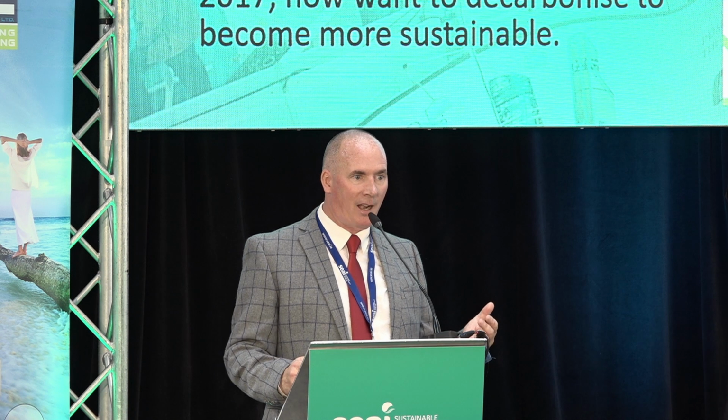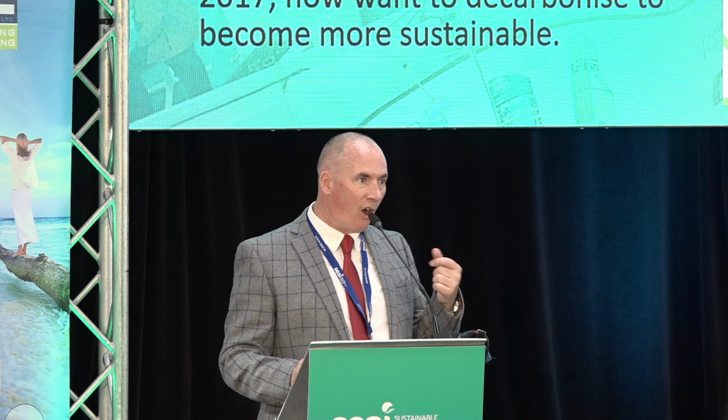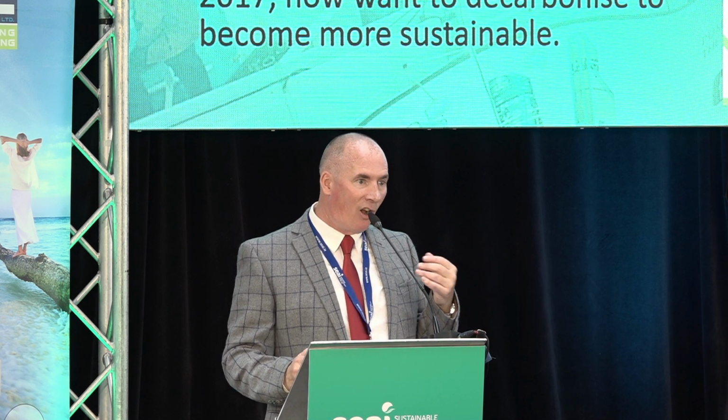It's a three-part, one-hour series of presentations that we go out and deliver to building engineers. And we basically explain how to design systems. Now, there were obvious challenges with regard to retrofit. A lot of the buildings pre-Part L were designed for heaters, boilers and chillers. Consequently, the pipework, the flow rates, the temperatures, everything in the system was designed for temperatures that typically a heat pump couldn't deliver. So there was new technology, but there also had to be new design. So we had to look at the technology we're using, the design of how we implement it, and also the control strategy, which is extremely important.